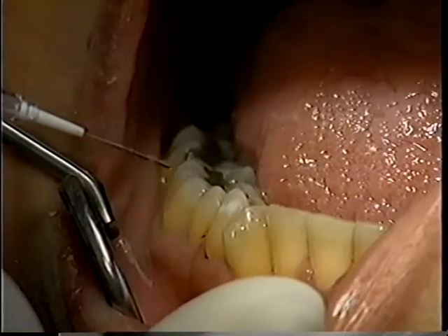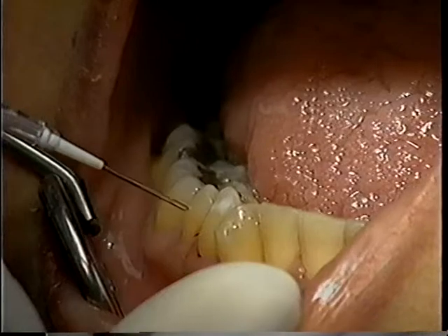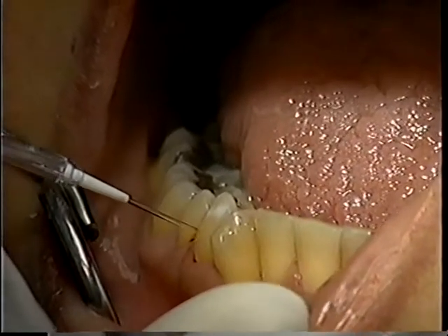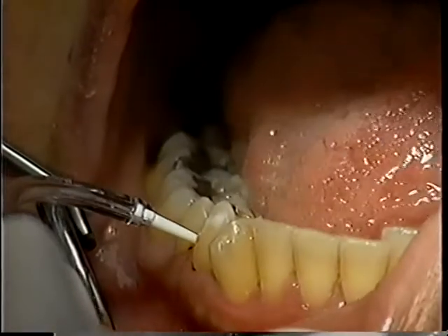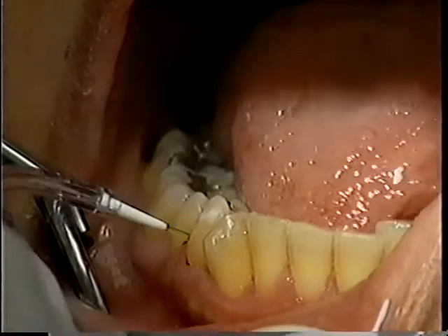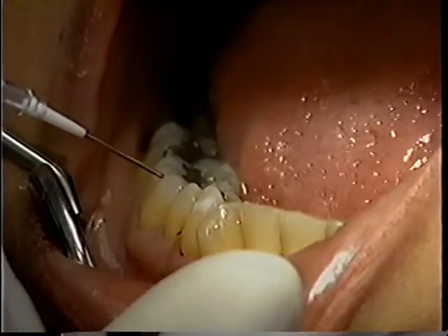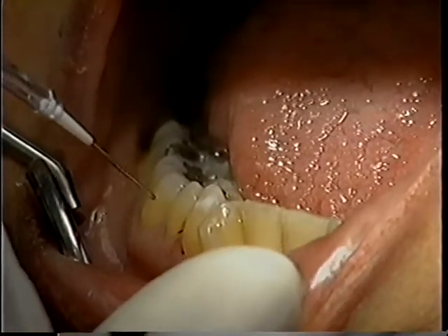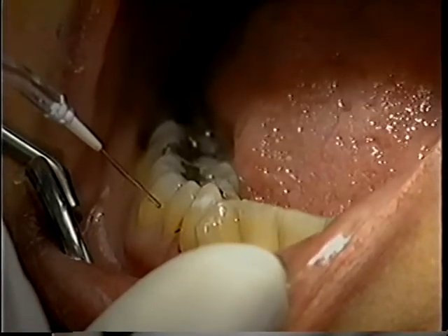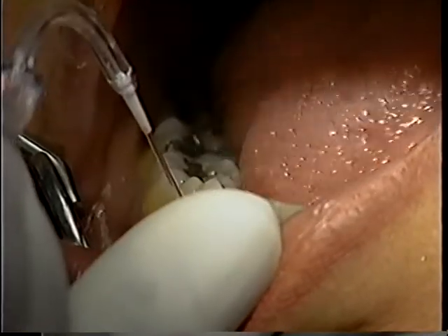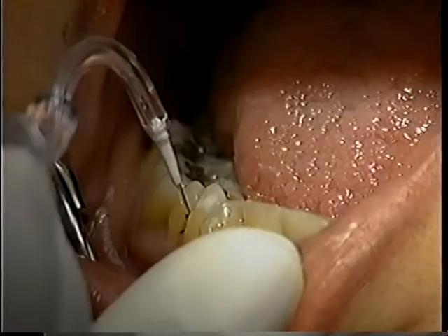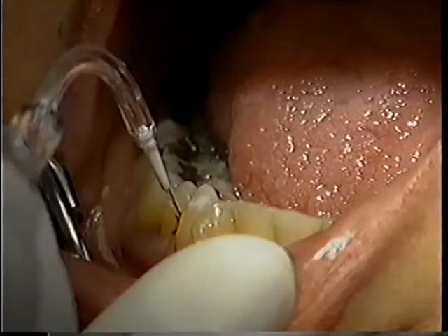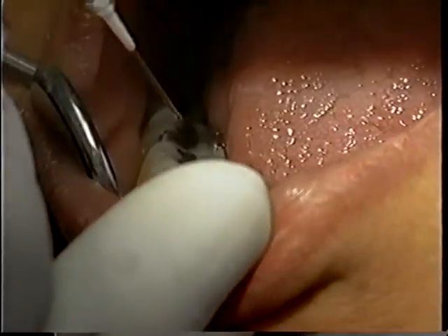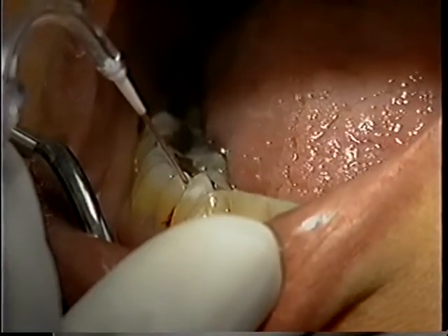Sometimes you get a false reading when the probe tip is not placed within the pocket but actually goes through the embrasure. In this situation, I have a good feeling that there isn't 4 millimeters of pocketing, there probably is less. I'm going to go back in and back up the computer and reprobe it. And here we have 2 millimeters of probing, which is much more accurate.